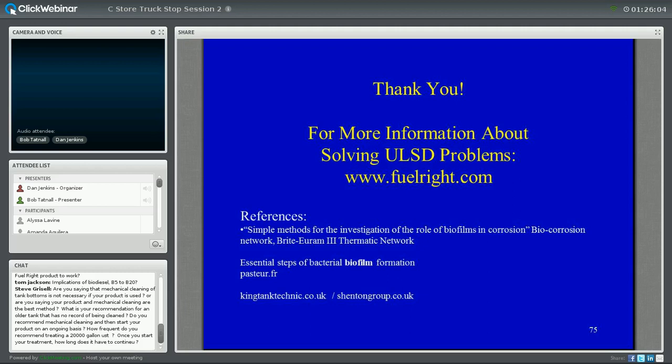So we're concerned about that as much as we are the other problems that happen in contaminated fuel systems. And I determined in my earlier testing that with 5 or 20% biodiesel blends, standard dose rates do not prevent black honey. They control corrosion. They control sludge as we know it, but they don't control the black honey problem. And it's appearing now in my current testing that maybe double dosing will. So I'm not proposing everybody rush out and start double dosing the world right now. But I'm just saying that it's a continuing study, and if you see anything that looks to you like black, sticky, lightweight tar that is very, very hard to clean off of things and get off your fingers and off of equipment, think about it. Give me a call. We might be able to prevent that too, but it's going to take a higher dose.